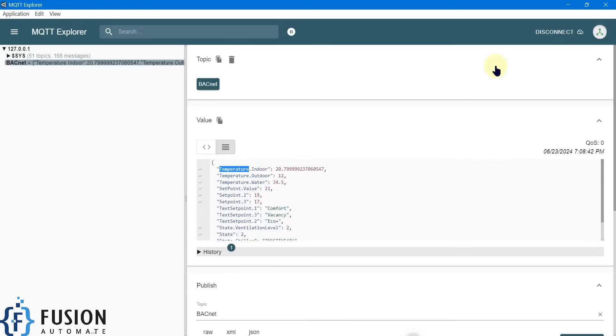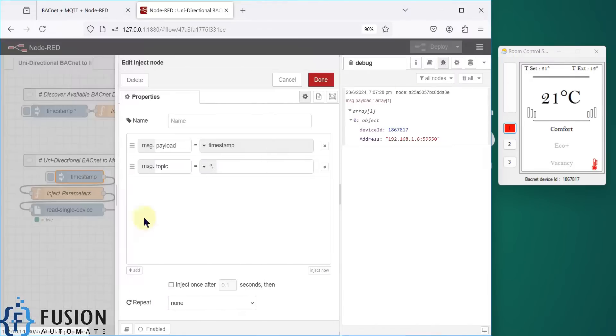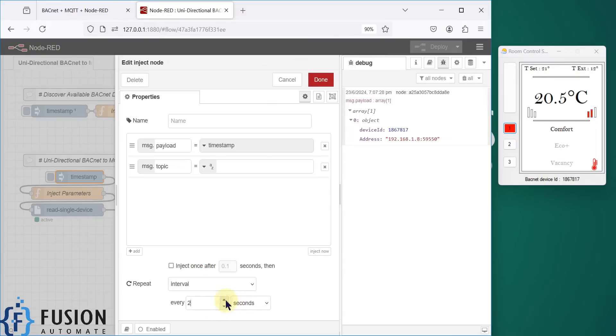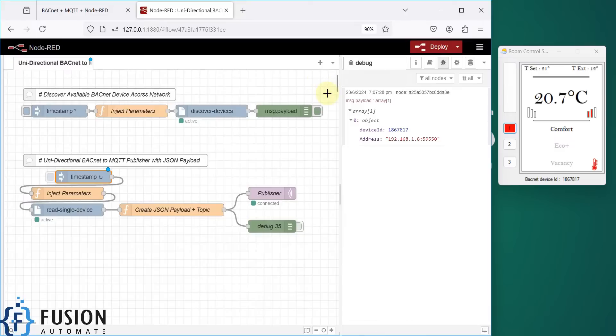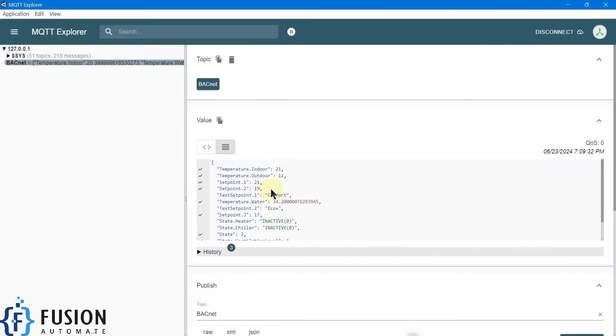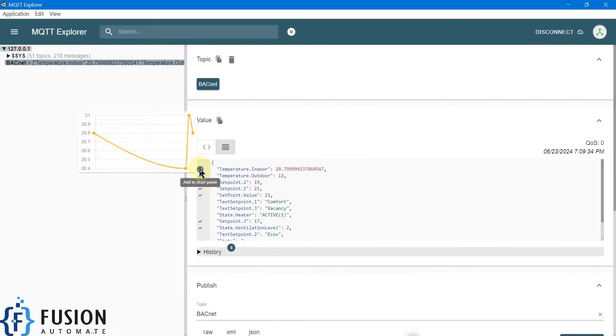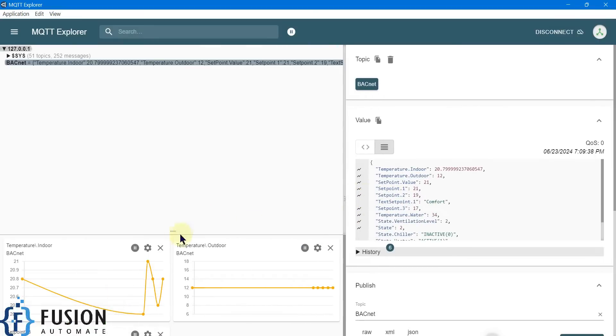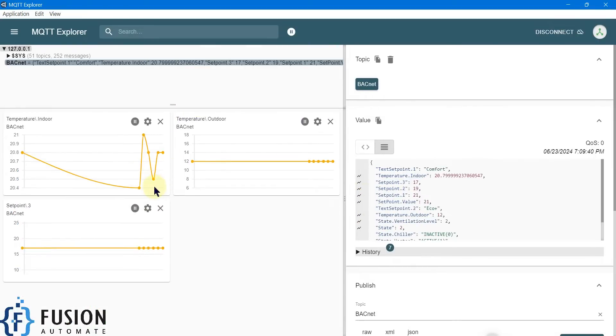It reads the point value and point name from the BACnet device and publishes the point name along with the point value to the MQTT topic — the BACnet topic. That is how it works. I can set the interval to two seconds, press Done, and deploy the flow so it reads and publishes data to the MQTT broker every two seconds. We can take a graph of this data and monitor it.